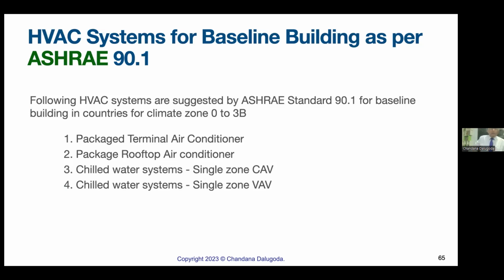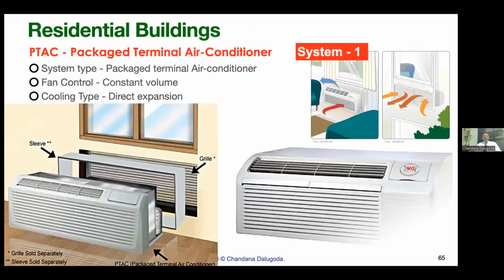Then a baseline building, as per ASHRAE 90.1, these are the air conditioners you must use for a building net zero. Package terminal air conditioners, package rooftop air conditioners, chill water system single zone, constant volume, and variable air volume. Let's see what it is. Residential buildings, we should use PTAC, package terminal air conditioner. Of course, we don't have that particular unit here in Sri Lanka, probably split units with a higher EER. Remember, EER, that is energy efficiency ratio, should be equal to or greater than 11.3. Unfortunately, in Sri Lanka, whatever we bring here, EER is 9 to 10.